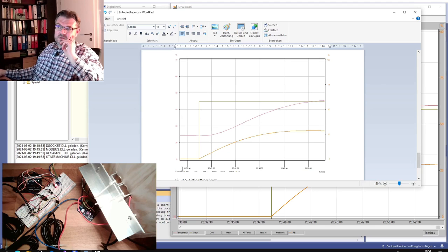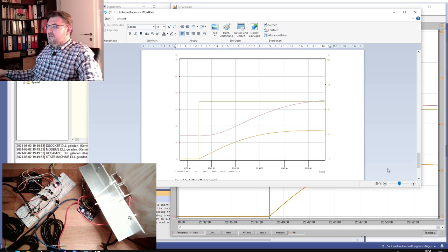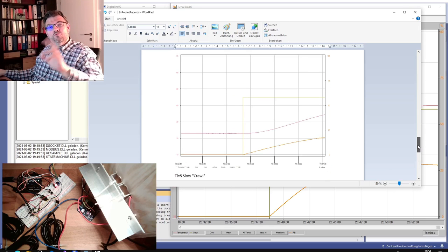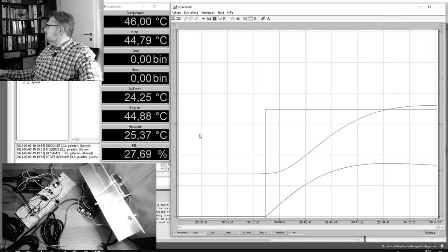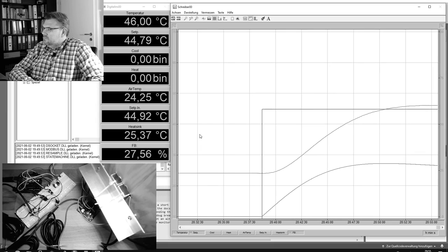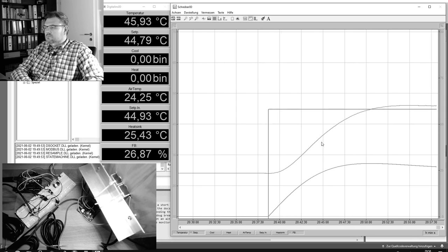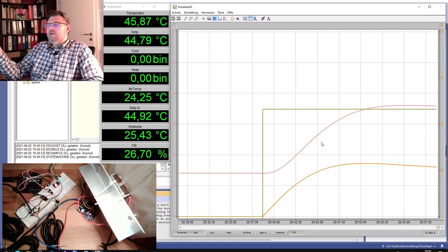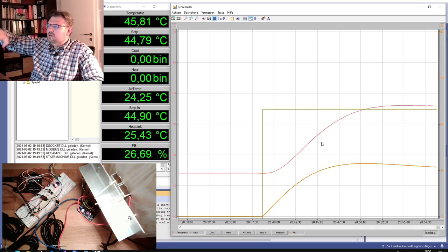but it looks exactly like I've shown you in this one video where I explained the I controller. So this is actually how it looks, and those things will happen if an I controller is too slow or too fast. These are the things which will happen. Yeah, you see, at least it's stable. It will now drop very slowly to the set point, and then it will keep.